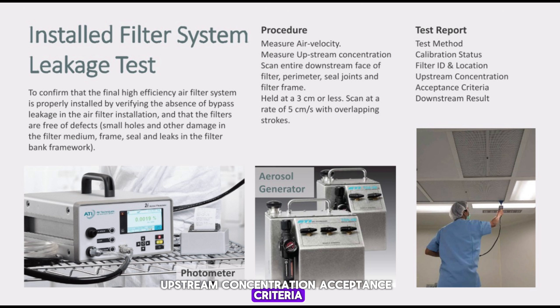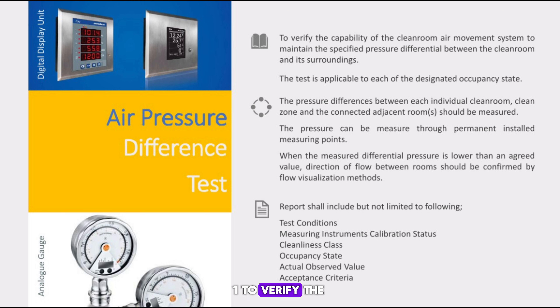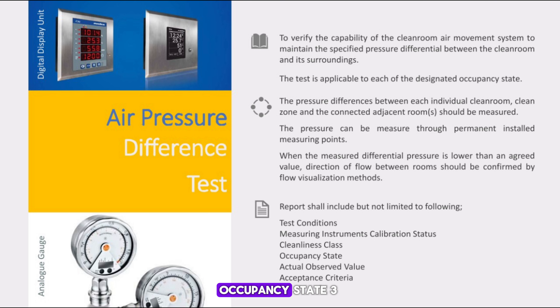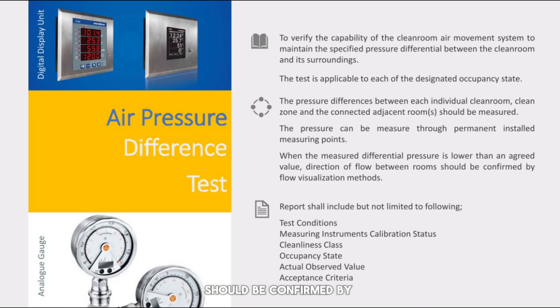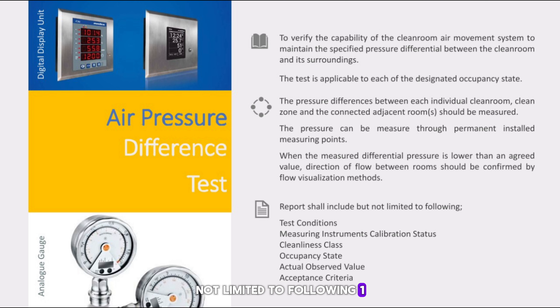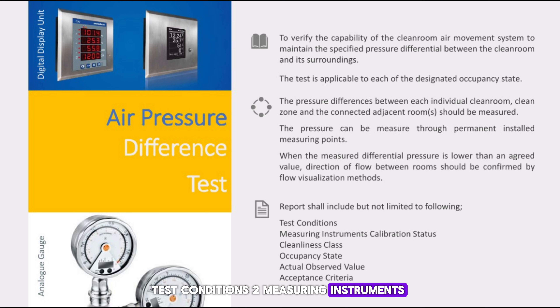Air Pressure Difference Test — Purpose: to verify the capability of the cleanroom air movement system to maintain the specified pressure differential between the cleanroom and its surroundings. The test is applicable to each designated occupancy state. The pressure difference between each individual cleanroom, clean zone and connected adjacent rooms should be measured through permanently installed measuring points. When measured differential pressure is lower than an agreed value, the direction of flow between rooms should be confirmed by flow visualization methods. Report shall include: test conditions, measuring instrument calibration status, cleanliness class, occupancy state, actual observed value, and acceptance criteria.